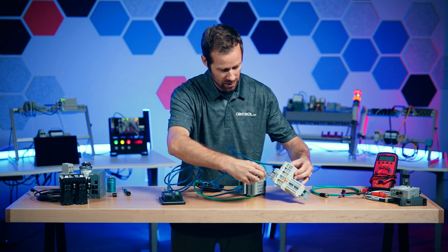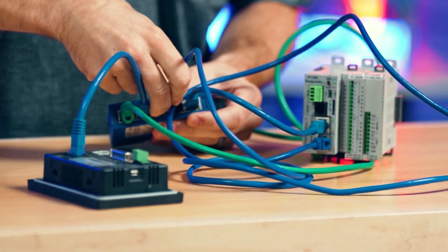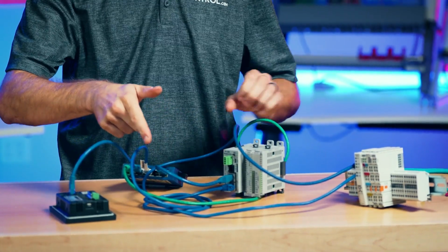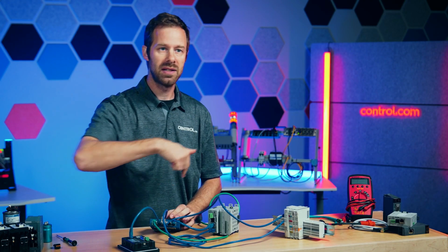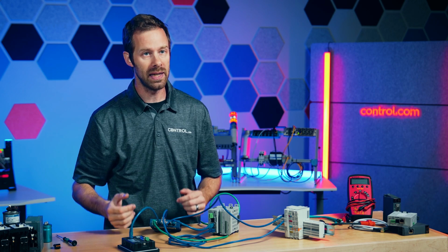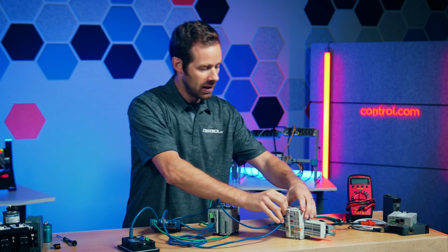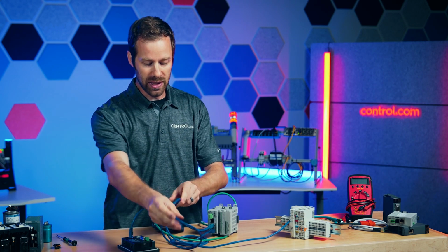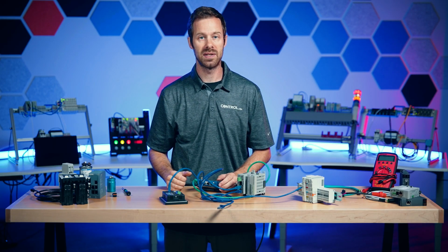Now, from this second connection, we can return back to the original network switch. So our signal comes out from the switch to the controller, to all the other devices, and then returns back to the network in a big loop. That's why they call it ring. Now let's see what happens if one of these cables gets disconnected, jostled, broken, and we lose the signal. But it's okay because we still have a route that's connecting all of our devices together, giving us that extra protection and redundancy.